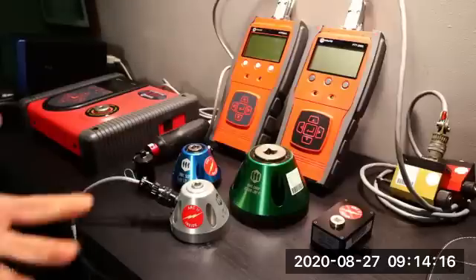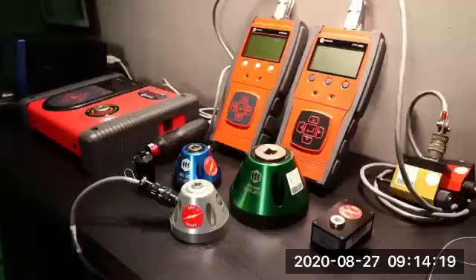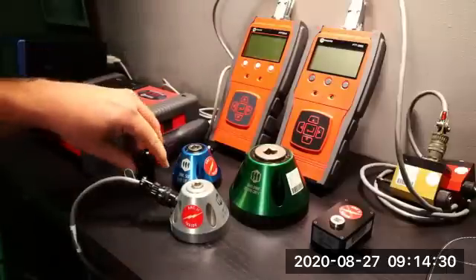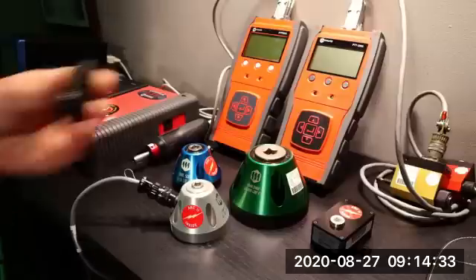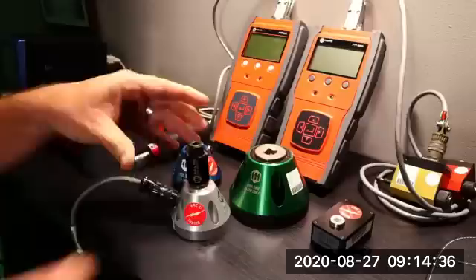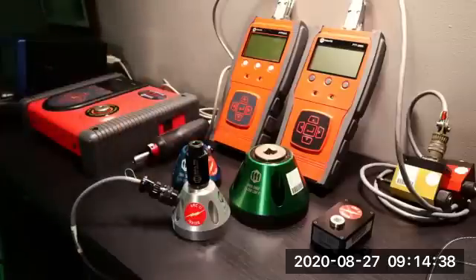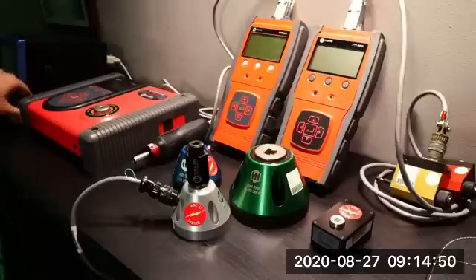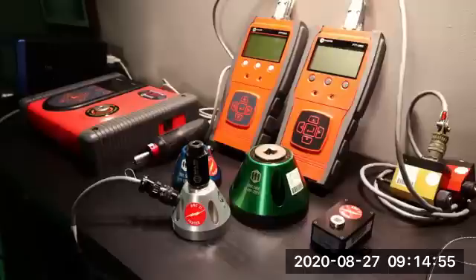Now, if we want to use this style of analyzer for a dynamic tool, such as an electric clutch screwdriver, we can do that as well. We do need to add a rundown adapter to the sensor. The rundown adapter allows the tool to get to its operating RPM speed. We have a series of washers inside the rundown adapter that will compress, allowing us to simulate what the joint characteristics might be for a specific rundown.